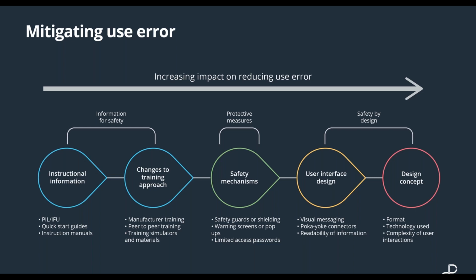risk. So if you find something in a formative which has the potential to cause patient harm and comes up in your risk analysis as something important, and it didn't come up in any of the other formatives for some reason. Maybe something's changed in the market that means people are approaching using a product in a new way that hadn't come up in all your previous formatives. If something pops up right at the end of the process and there's feedback on the user interface that affects risk in a way that the regulators are going to be concerned about and has the potential to cause harm when it's in the market, then really you have to make those changes.